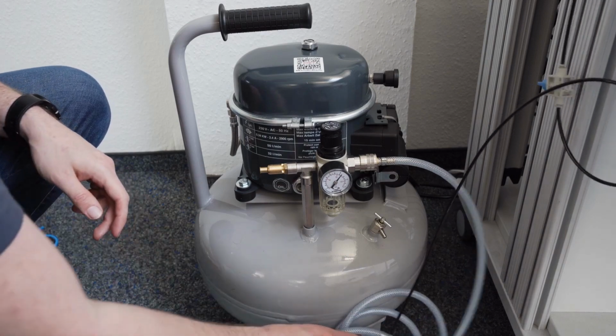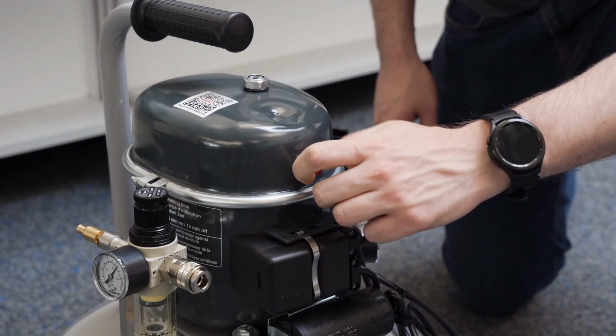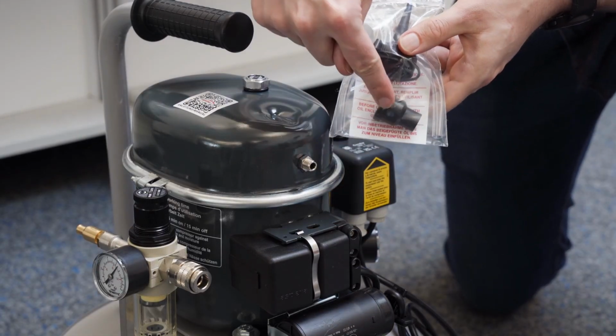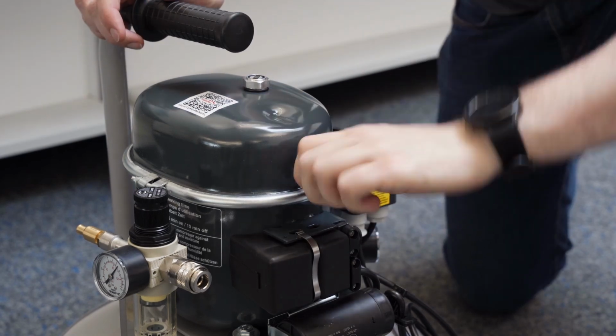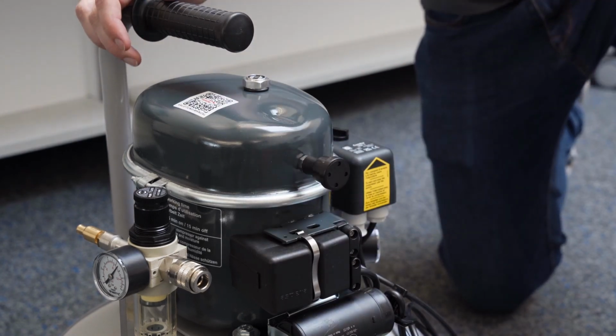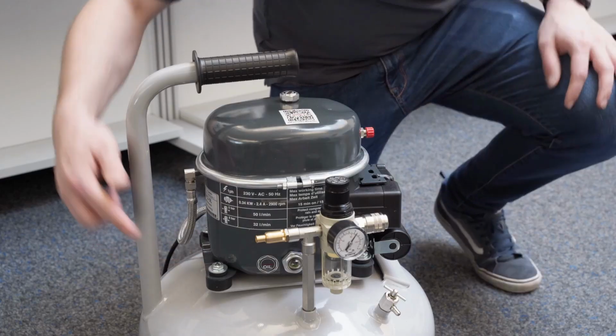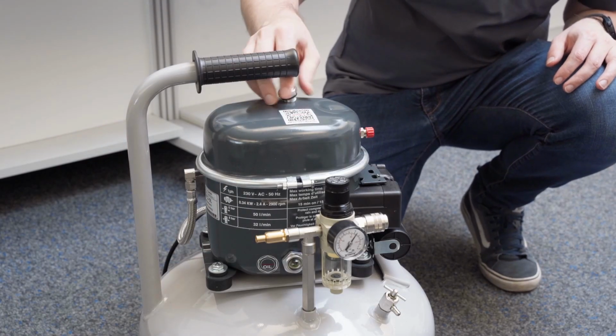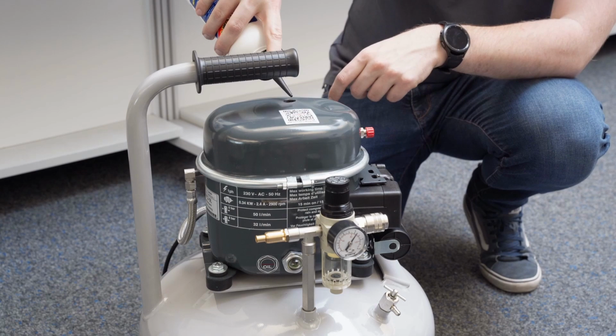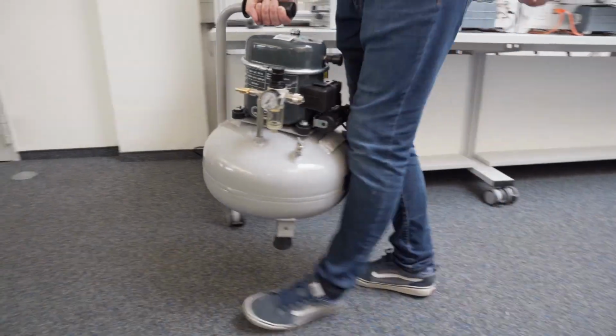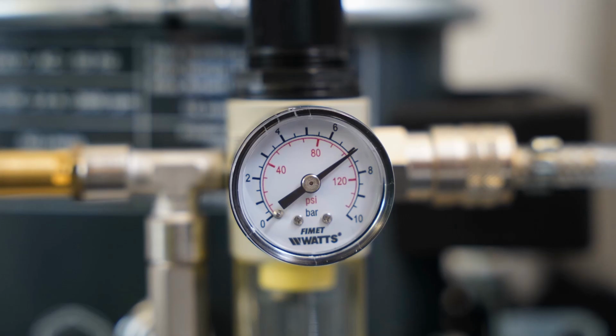If the lightweight compressor we offer is used, we first ensure that the air filter is attached to the air inlet. Additionally, the compressor should contain enough oil. The oil level must be in the middle of the sight glass when the system is turned off. The oil level should be checked regularly and refilled if necessary. Approximately 7 bar is required for the operation of the system.